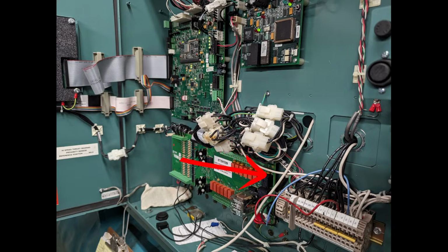Over here we've got actual mechanical relay contacts handling our outputs and heavy load pass-throughs. For example, these relays handle your oil heater, which passes through them to get engaged and powered to maintain oil temperature in the sump. That's the primary function separating the I/O board from the micro board, and why they're two separate boards with those two different functions.